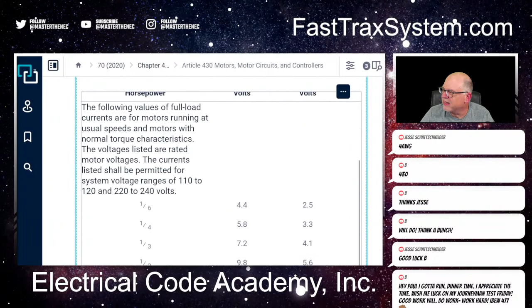This is 430.248, and we're looking at a 7.5 horsepower. So right here, 7.5, right there. And we need to go over to the 208 volt column right here. So we'll just follow that down, and that is 44. So we'll write that down - that's your FLC, 44 amps.